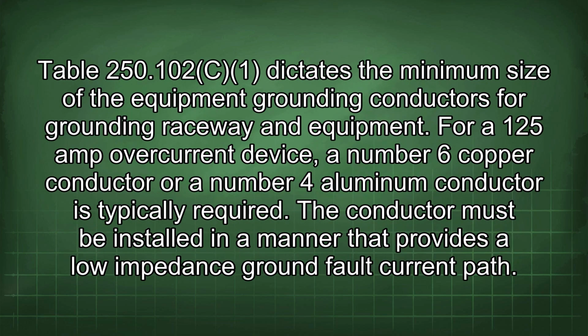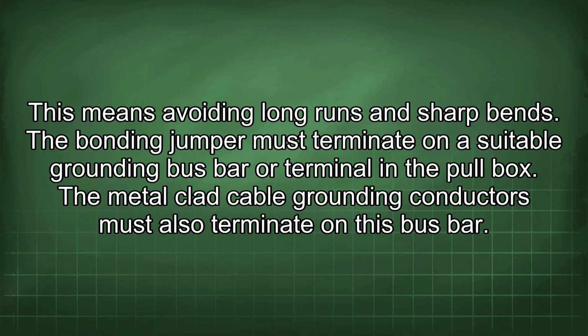Table 250.102(C)(1) dictates the minimum size of the equipment grounding conductors for grounding raceway and equipment. For a 125 amp overcurrent device, a number 6 copper conductor or a number 4 aluminum conductor is typically required. The conductor must be installed in a manner that provides a low impedance ground fault current path. This means avoiding long runs and sharp bends.